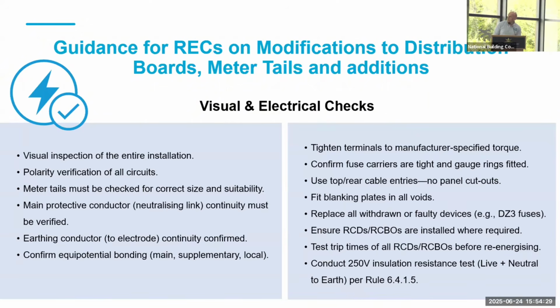The meter tails must be checked for correct size and suitability. Again, the main protective conductor, which is the neutralising link, continuity must be verified. So what they're referring to there is the earthing system. In Ireland, our earthing system has to be TNCS on the majority of installations. So we have to confirm that, because again, from historic electrical installations done prior, in the 90s, they used to use a TT type earthing system. And the trouble with that is they used to use a 300 milliamp RCD, which hasn't been tested in decades, and they deteriorate. So we instruct registered contractors that they have to change that earthing system to a TNCS earthing system.